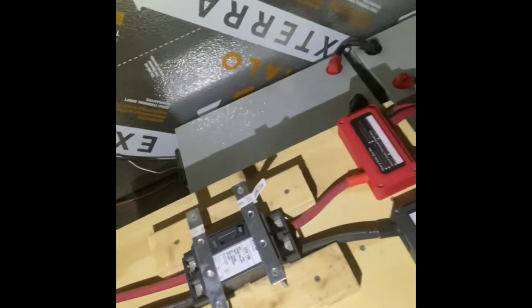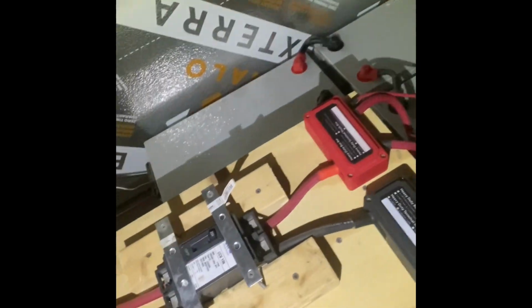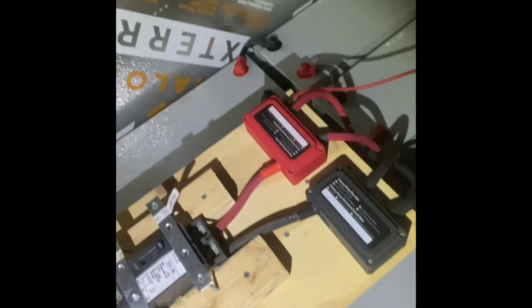So depending on how big your battery system is, you're going to want to make sure you have a decent sized wire to handle that current, because this is where it can get dangerous, on the battery to inverter side. That's where you can have sparks, wires overheating, and a lot more risk. Larger current, larger the risk.